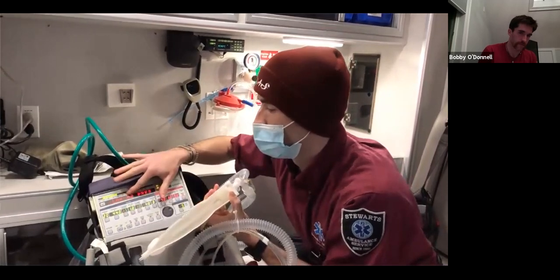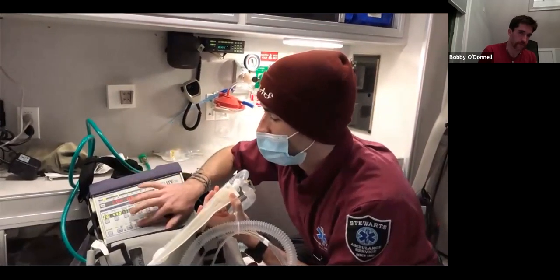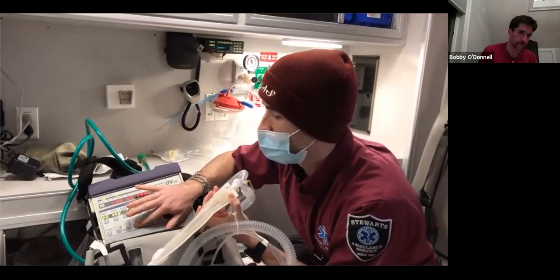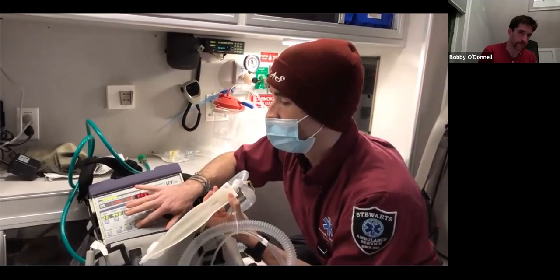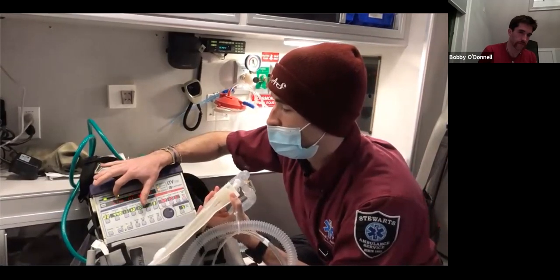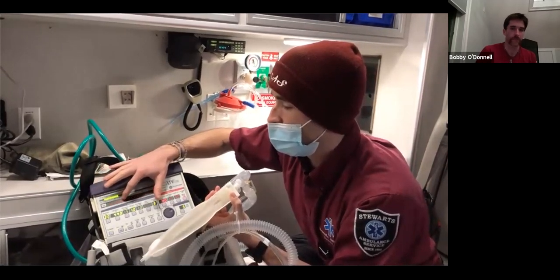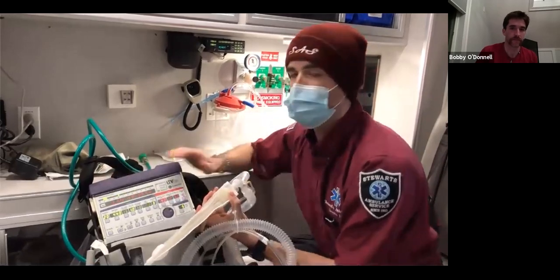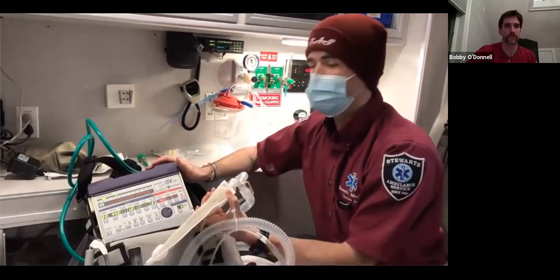It's not going to do it with the low O2 pressure alarm, but what I would do is when I see the inspiration, I'd push it once and then hold it in on inspiration. And it's going to give me a number here on the bar, but then it's also going to say P-plat with a number there. And again, we want that under 30. And that's it.